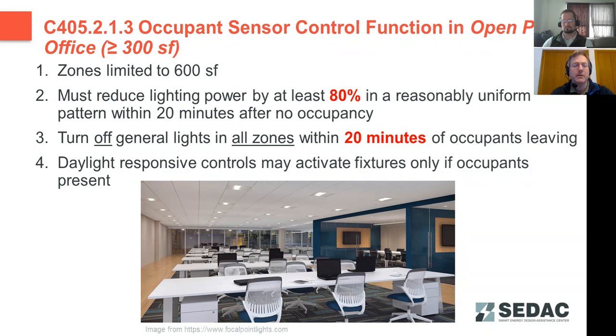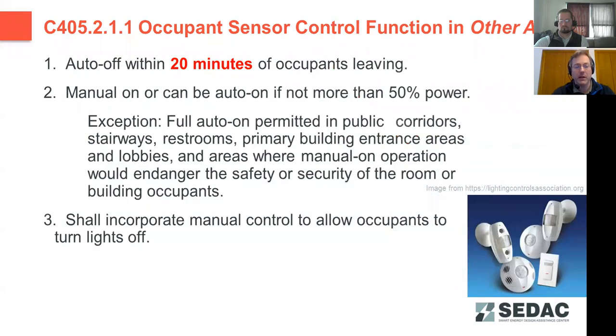More commonly, we'll just go ahead and turn all the lights off in a zone to reduce some of that complexity, which again, if you have complexity, makes commissioning harder. So this fourth point here, noting that the daylight responsive controls should not be overriding the occupant sensing controls, because we don't want all the lights to turn on once it gets dark out if there's no occupants to have the lights on. So the occupant sensors have first call of the lights, and then once the lights are on through the occupant sensing devices, then the daylight responsive controls will do the dimming and control on that.